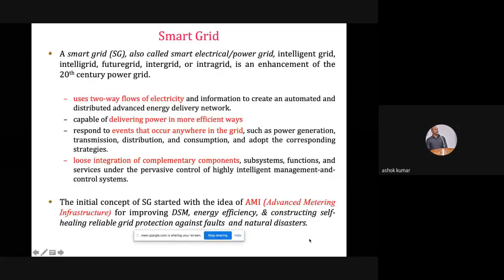So every industry should minimize the maximum demand, because if that maximum demand persists for a 30 minute time interval, that MD will be calculated. Let's say out of 10 MVA contract, if the industry goes to 9 MVA for 30 minutes, the entire electricity bill will be calculated for that 9 MVA. So advanced metering infrastructure was mainly included in India for implementing the smart grid concept, to reduce the demand of that particular industry.